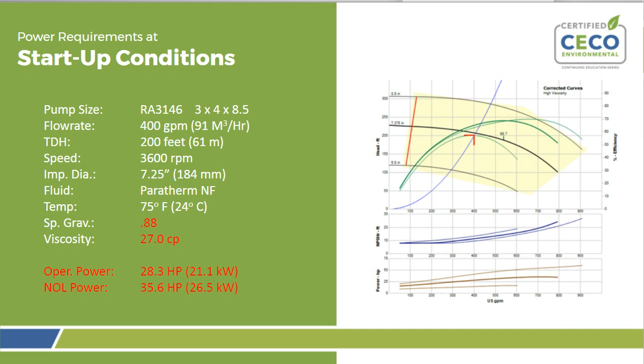So in this case, one always has to be aware of the changing fluid conditions at the different application points. You can't consider just your operating point. You also have to remember that this pump has to be started somehow, and it is going to be at an ambient condition when it does.